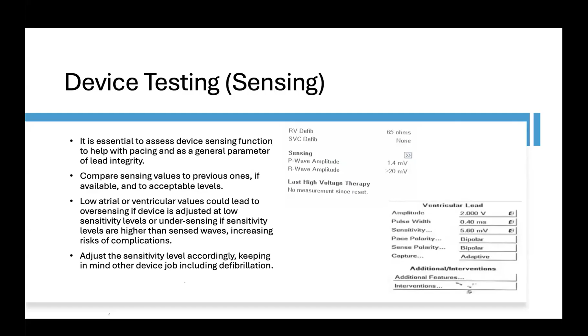This is the main thing, especially in ICD devices, if the R wave, let's say, is about 6, we have two things to keep in mind. Number one is that the device does not sense the P wave as an R wave. And on the other hand, we want to make sure that whenever those patients are going through a VF or VT, the device senses those. So we don't want to make the patient's ICD less sensitive by increasing the sensitivity, and at the same time, we don't want it to be very sensitive with low sensitivity to oversense the P waves or other signals on the leads.